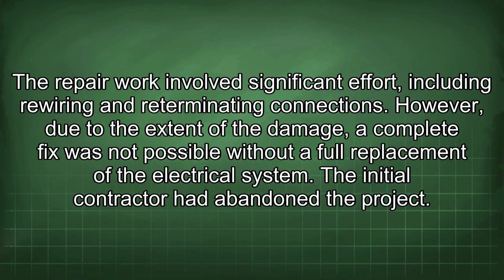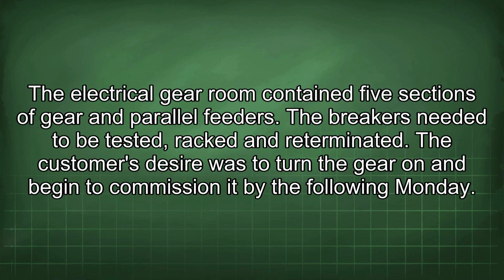The repair work involved significant effort, including rewiring and re-terminating connections. However, due to the extent of the damage, a complete fix was not possible without a full replacement of the electrical system. The initial contractor had abandoned the project. The electrical gear room contained 5 sections of gear and parallel feeders. The breakers needed to be tested, racked and re-terminated. The customer's desire was to turn the gear on and begin to commission it by the following Monday.